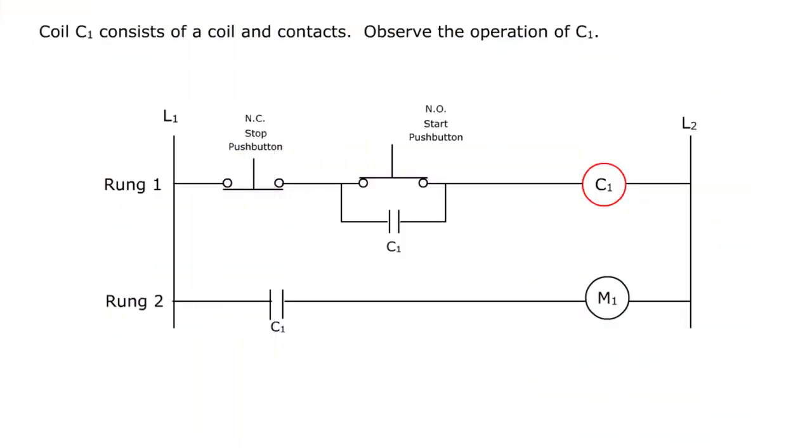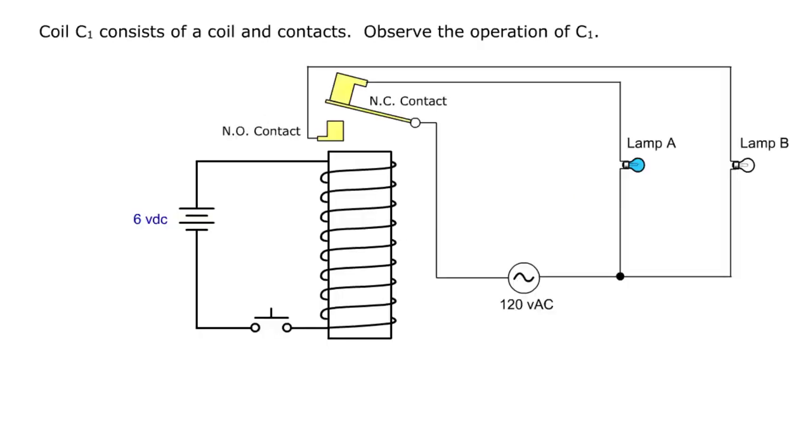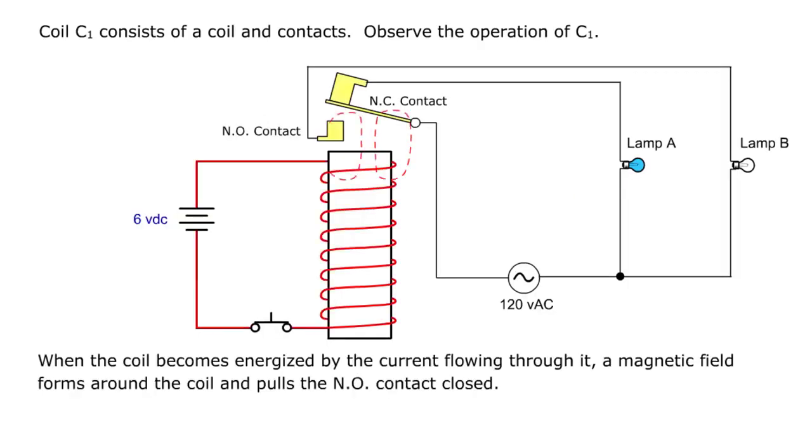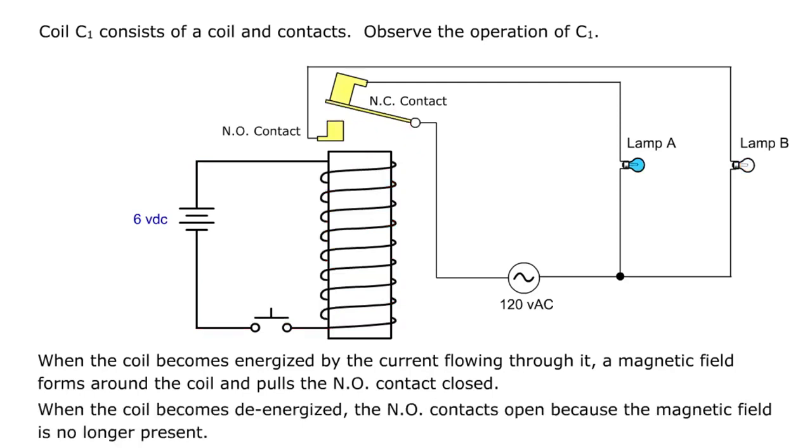Coil C1 consists of a coil and contacts. Observe the operation of C1. When the coil becomes energized by the current flowing through it, a magnetic field forms around the coil and pulls the NO contact closed. When the coil becomes de-energized, the NO contacts open because the magnetic field is no longer present.